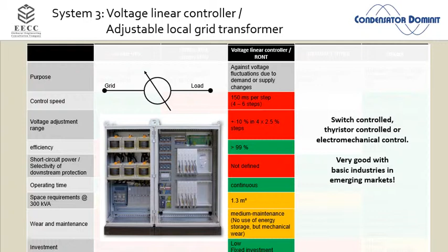All of those machines you can buy since about 40 years. And I saw them especially in, let's say, emerging countries with very simple industry. These machines are very valuable. If my voltage is changing over the day between minus 30% and plus 30%, just during the day, due to sunshine and no sunshine, then I can put in such a machine and it works nicely. But normally it does not protect you from voltage dips, because the time scale all these machines are working on is seconds, minutes and hours, not milliseconds.